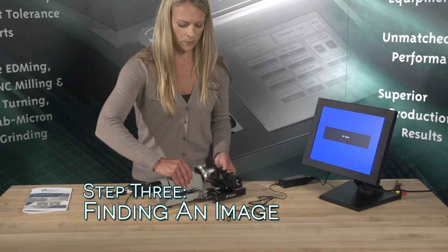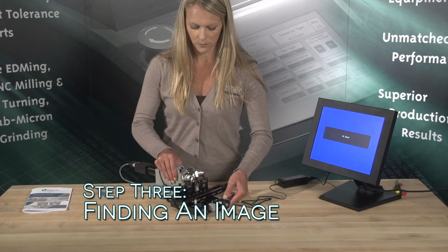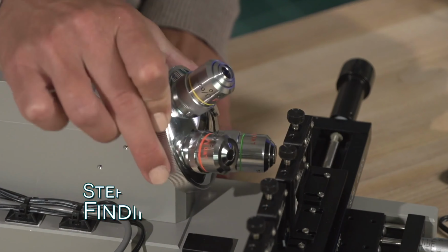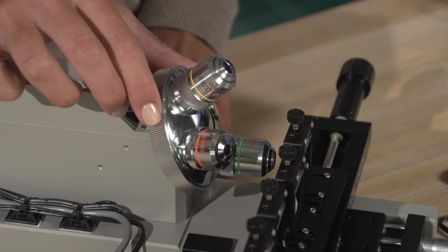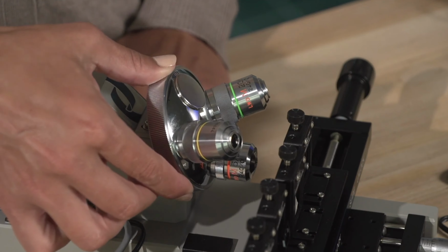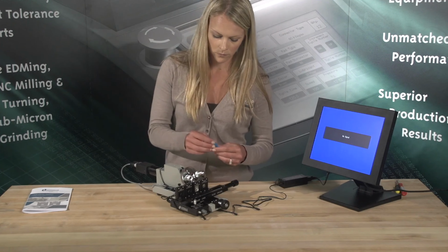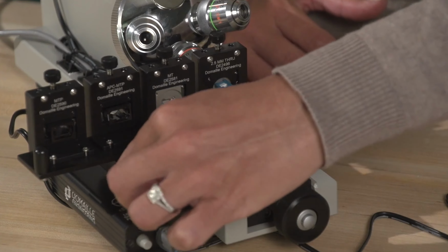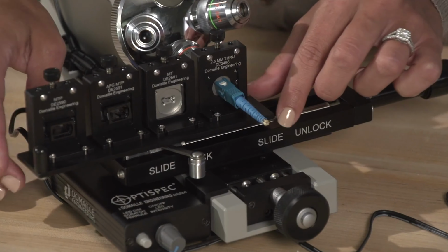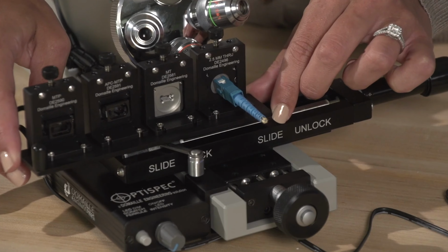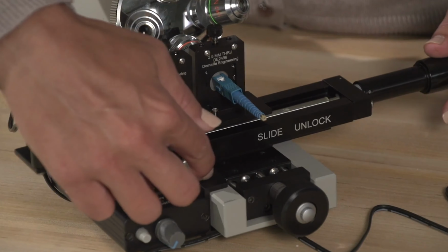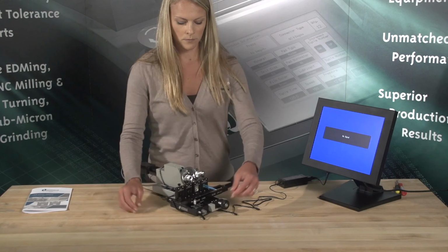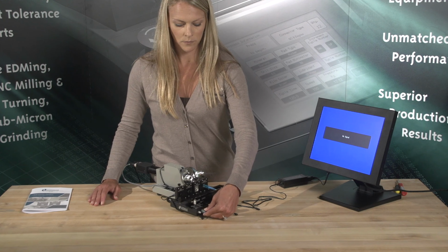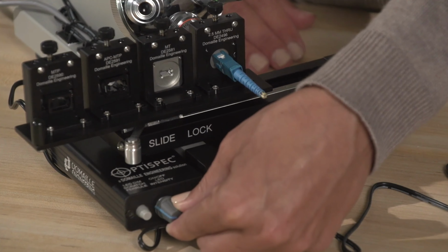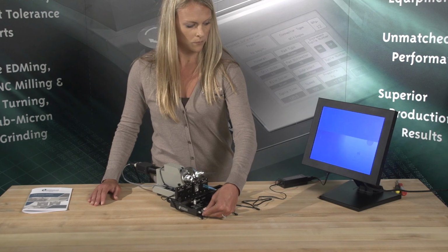Step 3. Finding an image. Turn the objective turret so that the 5x objective, indicated by a red line on objective lens, is at the 6 o'clock bottom position. Place a fiber connector in the appropriate adapter. Unlock the Velmex slide and move the adapter position so it is in line with the objective, and relock the Velmex slide. Power the microscope on using the LED intensity knob with the blue line located on the LED controller.